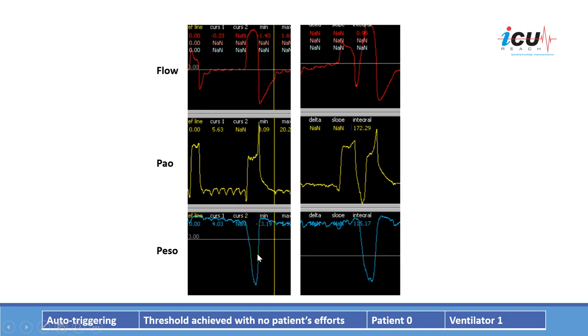Compared to a breath triggered by the patient — where a drop in esophageal pressure results in the patient's breath, the ventilator breath, and inspiratory/expiratory flow — in the auto-triggered breath there is no drop in esophageal pressure. The triggering threshold was achieved with no patient effort: zero breaths from the patient but the ventilator delivered a breath. This could be caused by a circuit leak, cardiac oscillations, or secretions.